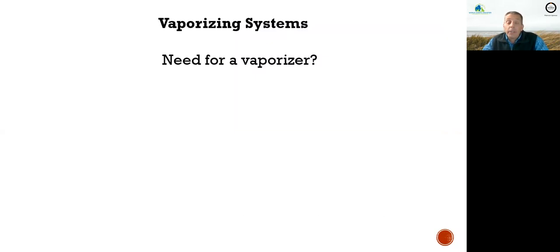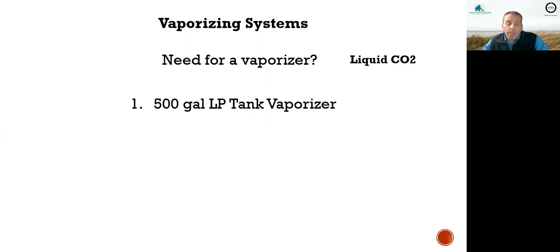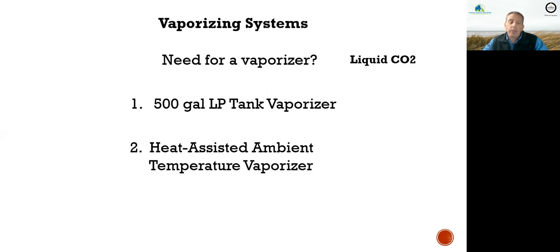We did build three vaporizing systems, but why the need for a vaporizer? Liquid CO2 comes in compressed form at negative 81 degrees and high pressure. We bring it down to atmospheric pressure and warm it up — hence the need for a vaporizer. Our first one was a 500-gallon liquid propane tank vaporizer — literally a liquid propane tank — which we use to help vaporize the liquid CO2.